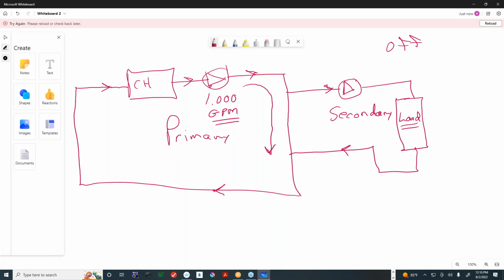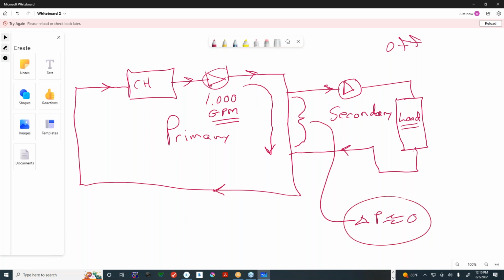And we say that where the first connection is here to the second connection, that differential pressure, let's just write that down here, delta P, is approximately equal to 0, which is sometimes where we come up with that phrase, a zero pressure bypass. So our primary circuit is running at 1,000 gallons per minute. Right now, the pump for our secondary circuit is off, so all the flow is going across the bridge, just like I drew the arrow here before. But the pressure drop from this point of the first connection over here, we'll call that connection A, and this connection down here, B, is approximately equal to 0.